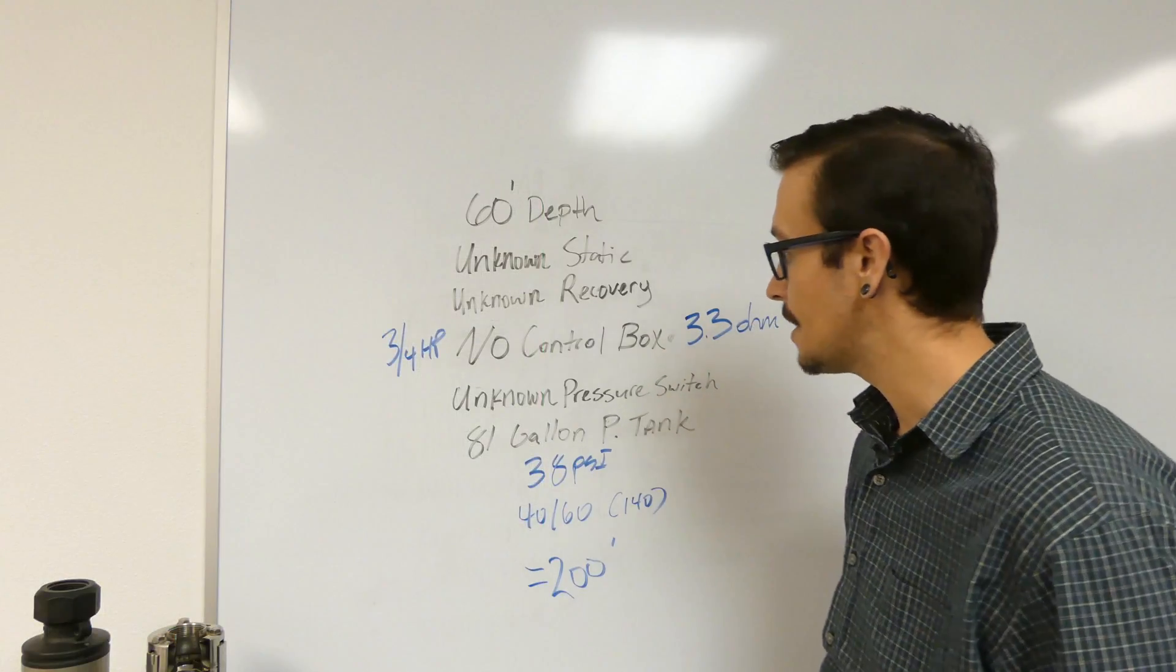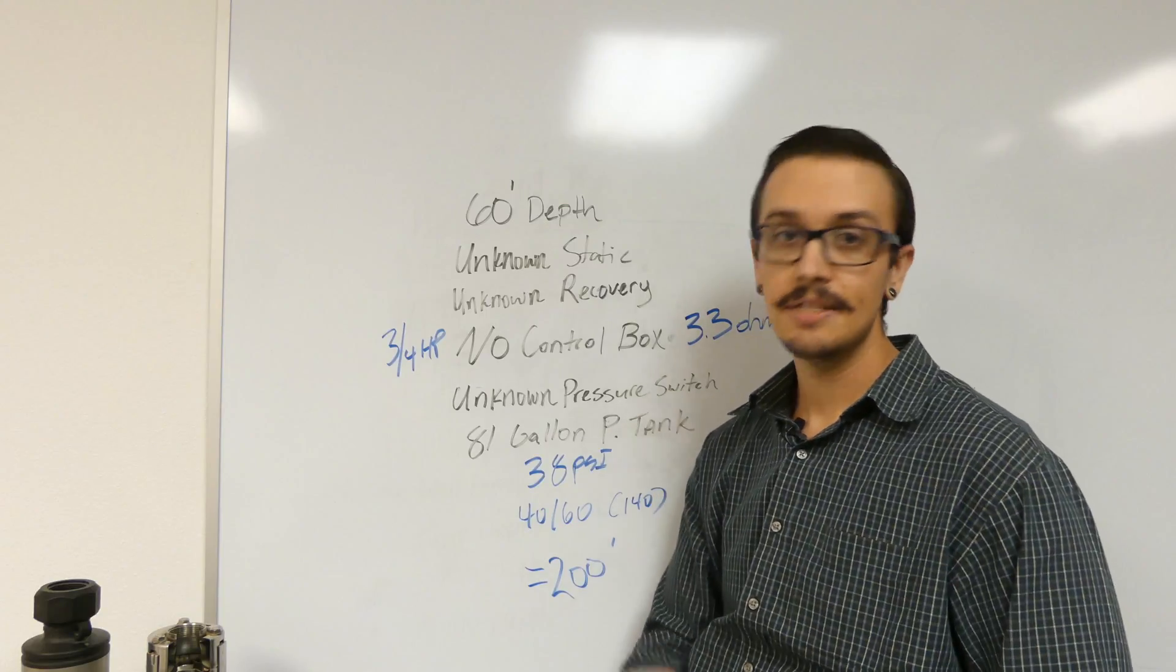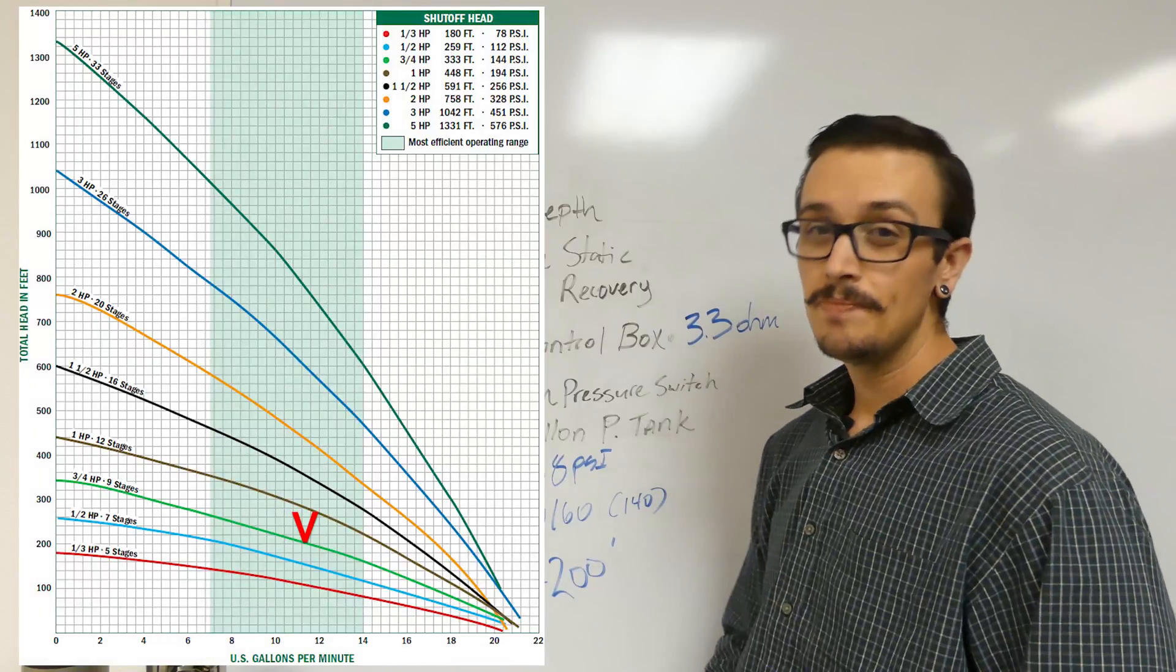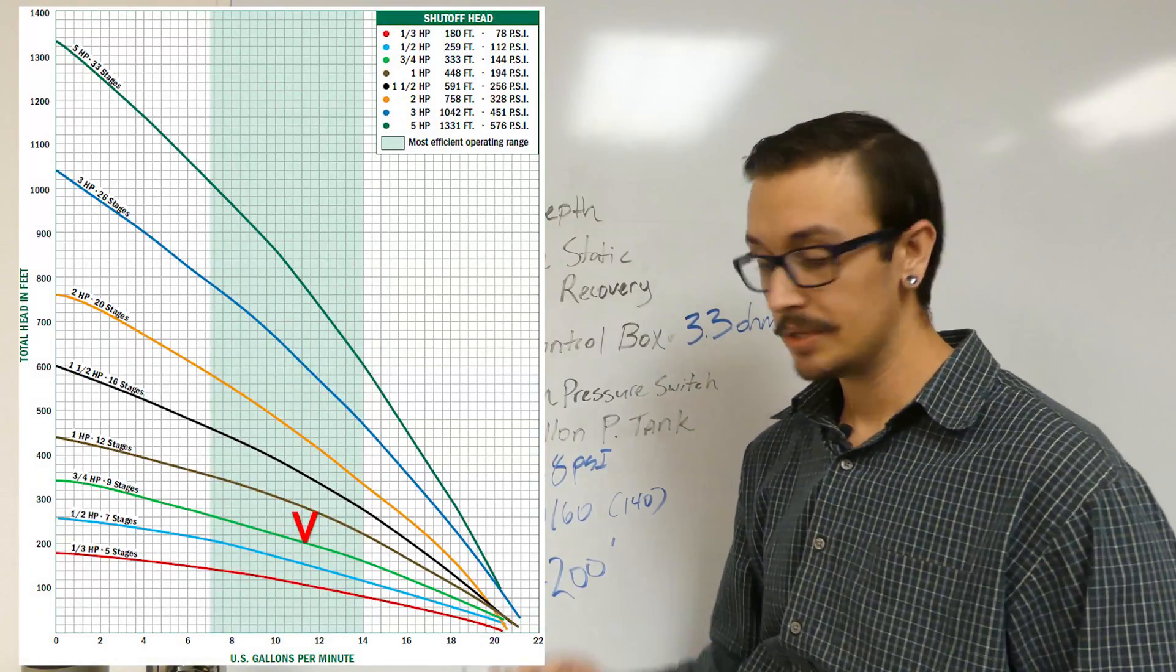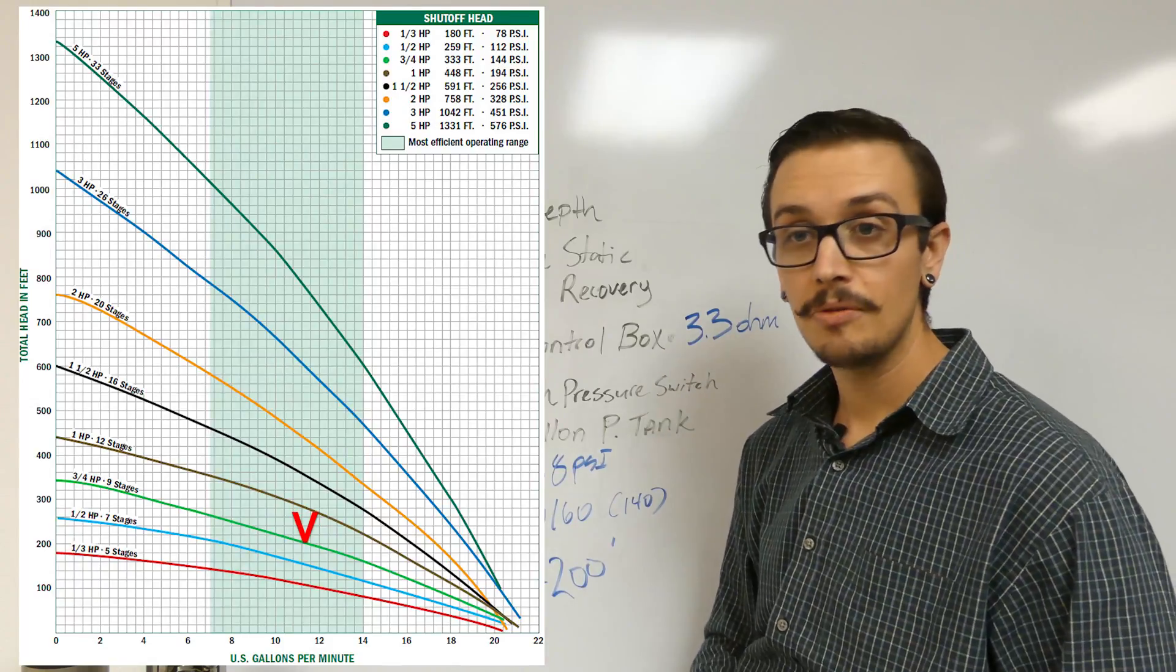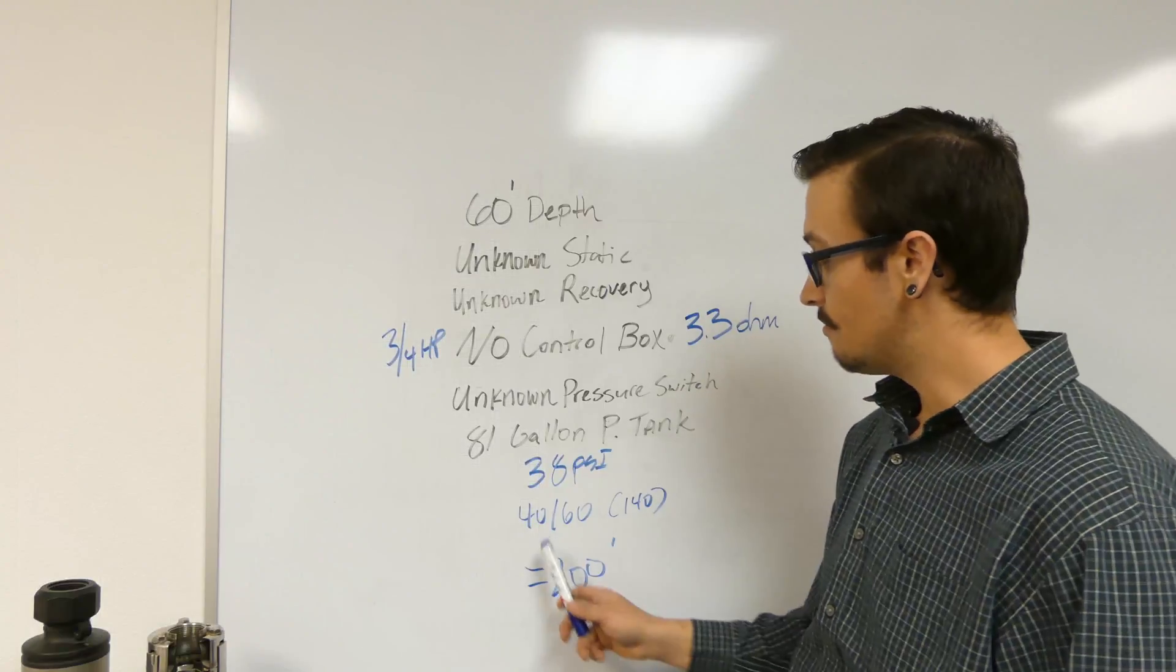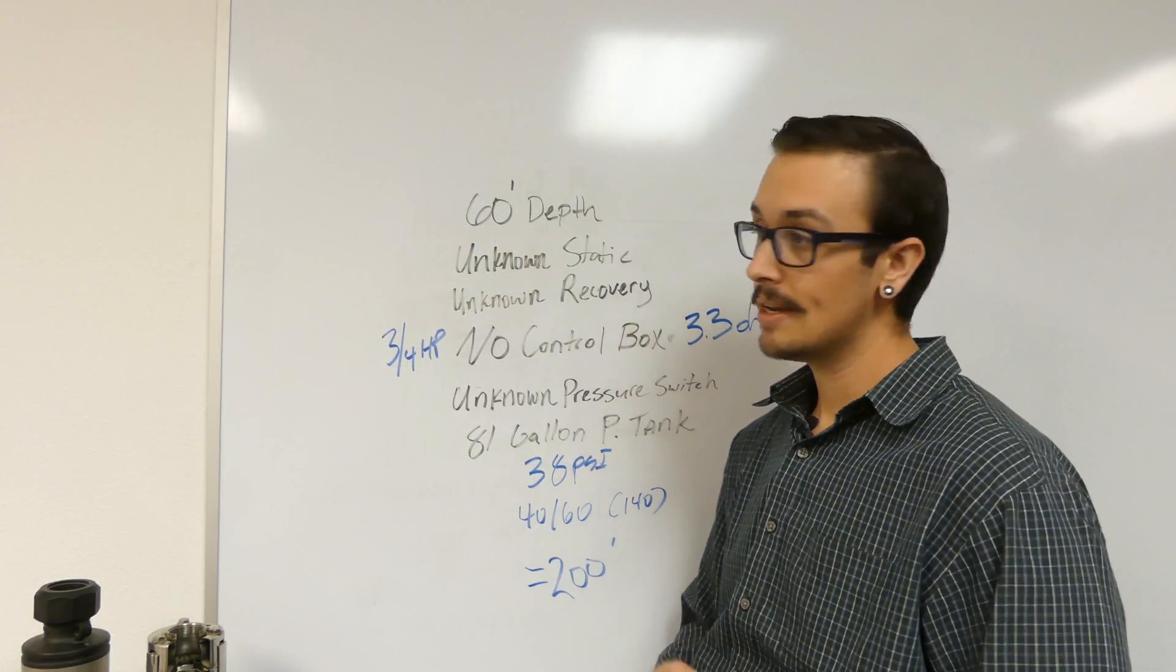So now let's just back way off and go to a 10 gallon a minute pump and see if that one looks like it might be a good fit. And what do you know, it happens to be a 10 gallon a minute pump. It's at a great spot in the pump curve. It will pump the entire range of the curve from 40 to 60 PSI wonderfully, and I have a lot of confidence that this would be the right pump.